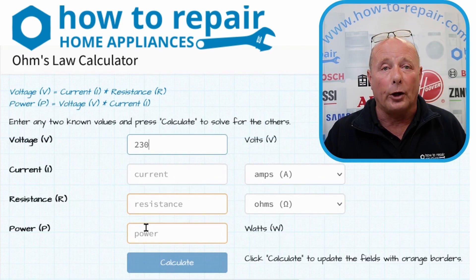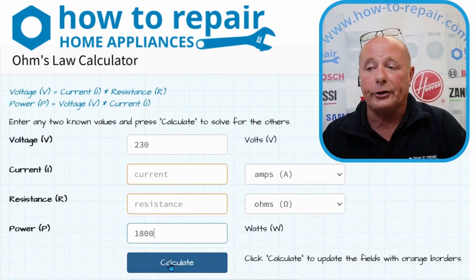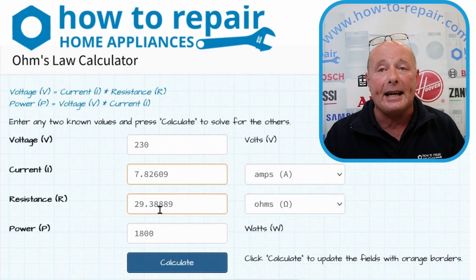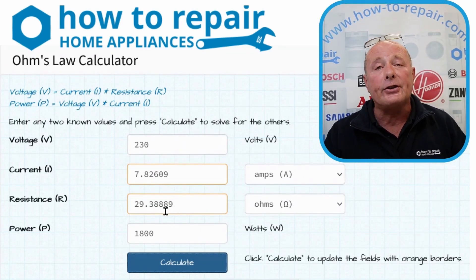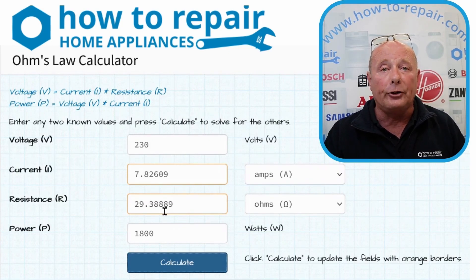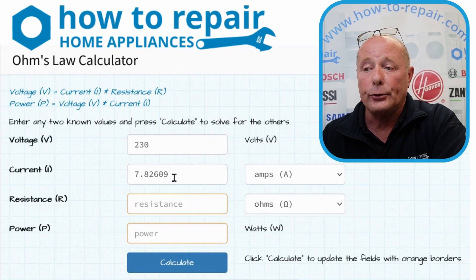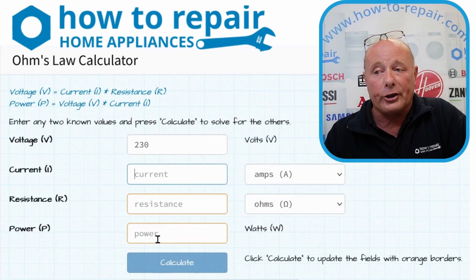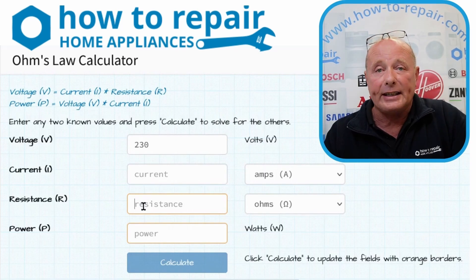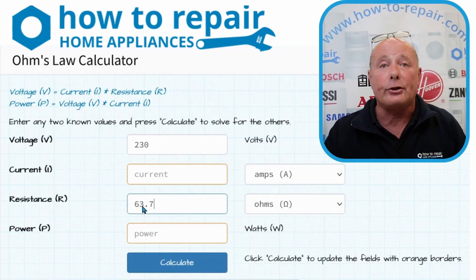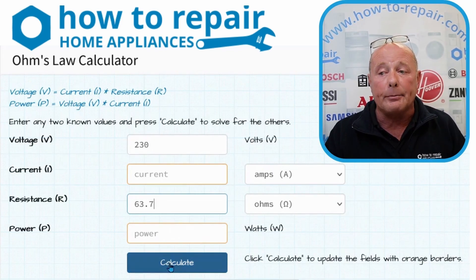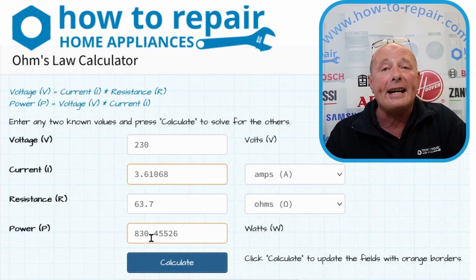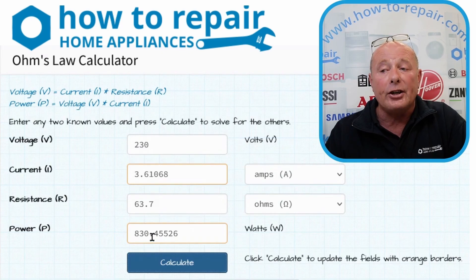We will be testing an 1800 watt element later. If we put in 1800 watts, we know that the Ohm's resistance should be 29.38 ohms on this element, allowing for a 10 to 15 percent margin of error on the multimeter and also the age of the element. The second way I use this is to work out the actual resistance to determine the wattage. When I tested the base element I had 63.7 ohms resistance but did not know the wattage at the time. The calculator tells me I should be looking for 830 watts — and the element was actually 850 watts, which is within that 10 to 15 percent margin.